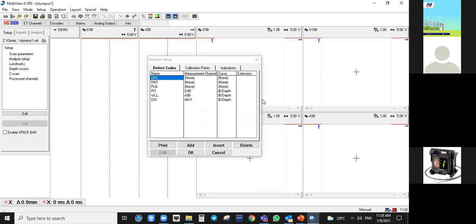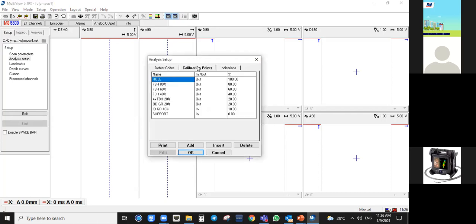Once you see this window, you'll see here calibration points. You click the tab, and these are the defects that you usually see in an ASME calibration tube. Now you need to add 3 defects. Press add here. The first that you need to add is big hole. You type in big hole. You choose between in or out. Of course, obviously it's not in, it's not out, but just put out. And then the percentage is 100%. So that's a big hole.